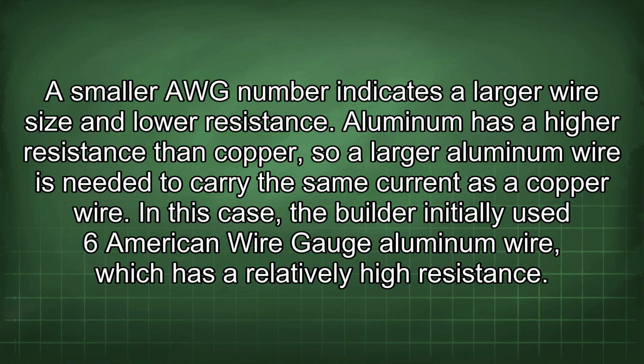Aluminum has a higher resistance than copper, so a larger aluminum wire is needed to carry the same current as a copper wire. In this case, the builder initially used 6 American wire gauge aluminum wire, which has a relatively high resistance.